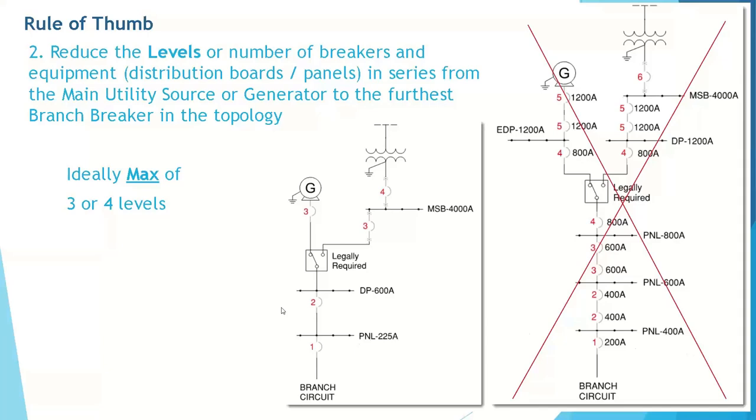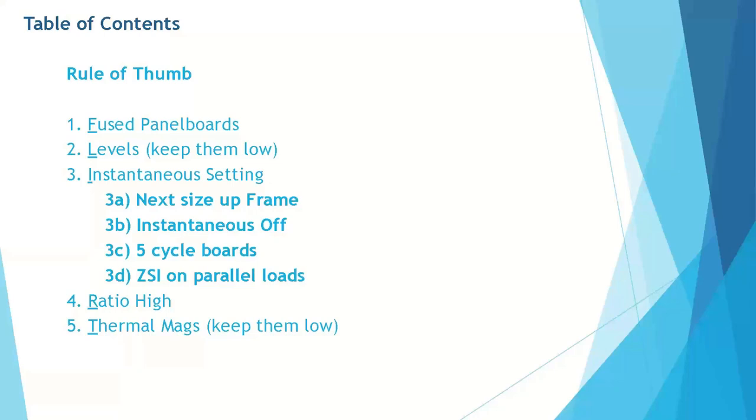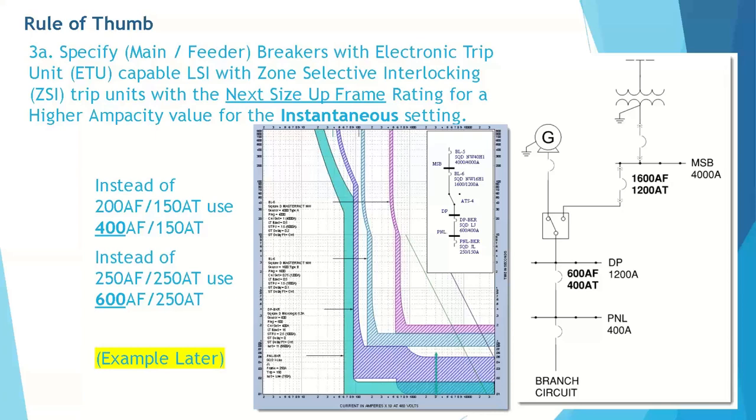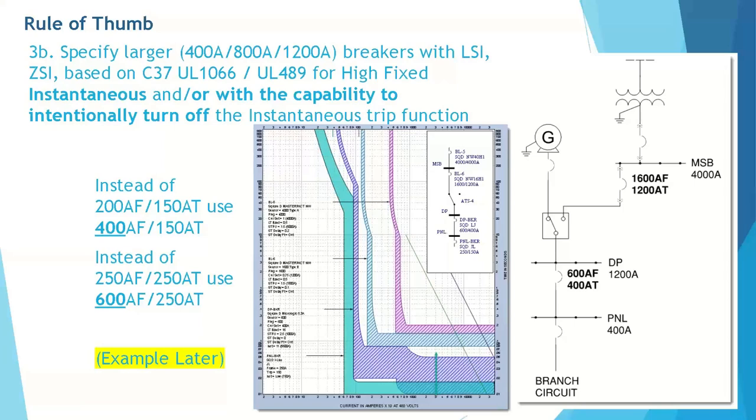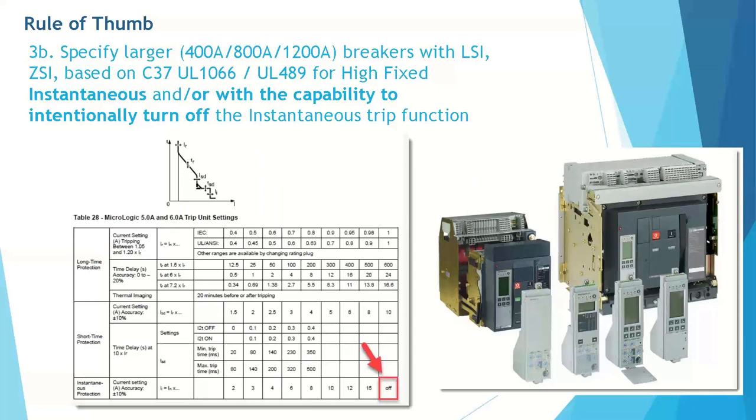This was an example system that we ran into and an optimal solution to that is often to redesign that system. Even though the main breakers have an exception, I would recommend removing the main breakers on feeders or bus risers when they don't meet the ratio test to simplify the system topology. The ideal maximum number of levels that you want in your system to selectively coordinate is three to four, as you can see in the revised single line. For the third rule of thumb for instantaneous adjustability, I broke it up into multiple parts that are very closely related. For 3A, it is necessary at times to provide the next size up frame to get a higher instantaneous setting.